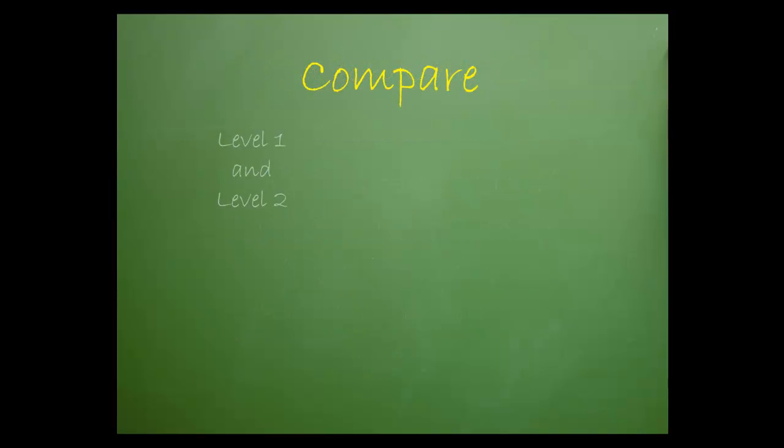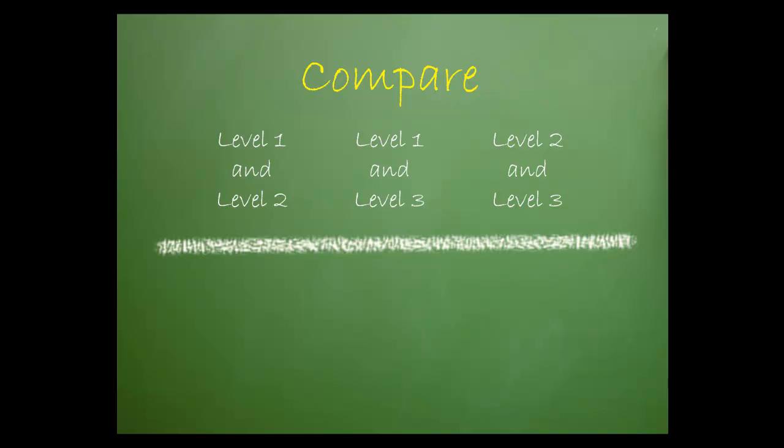The chart can compare level 1 and 2, level 1 and 3, or level 2 and 3. The chart can be built to compare results to the means and standard deviations of a consensus group, laboratory itself, or another instrument.